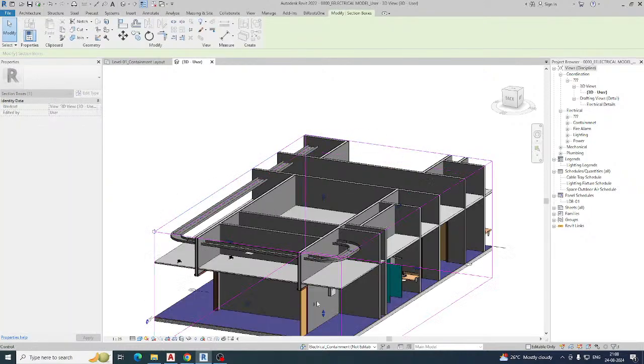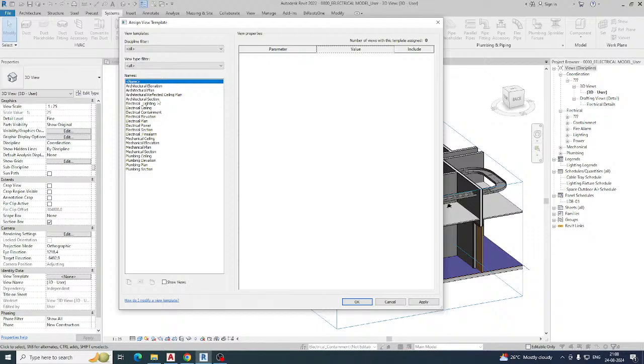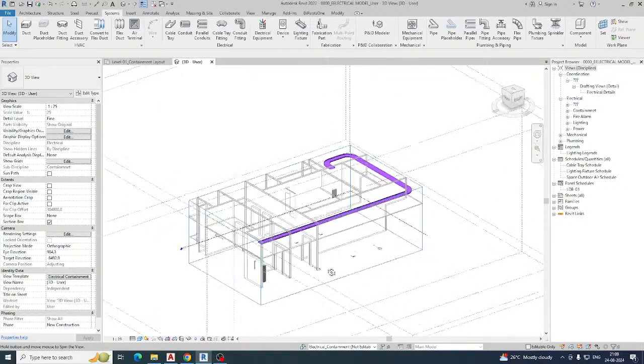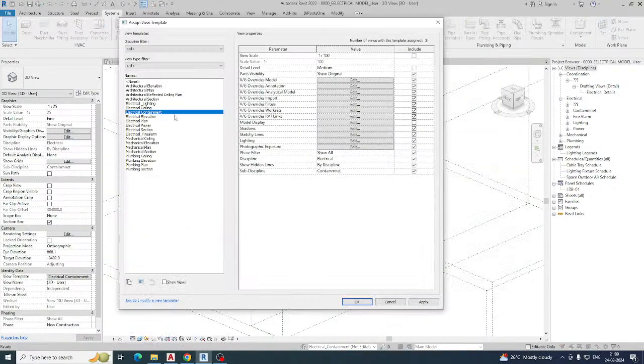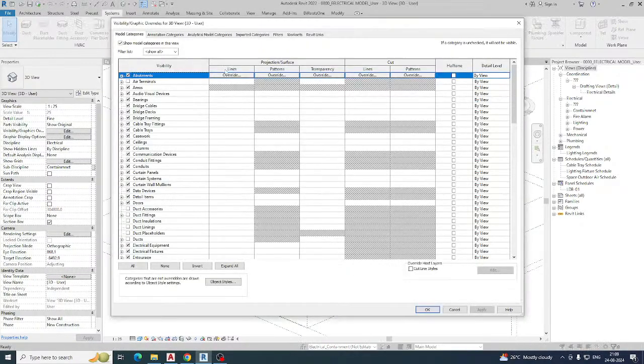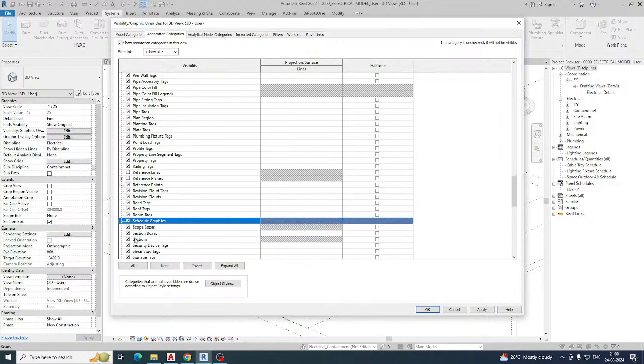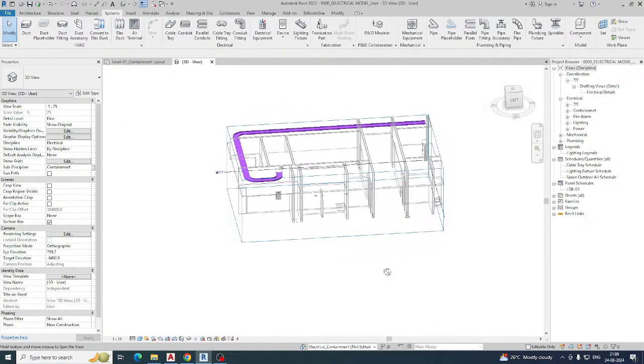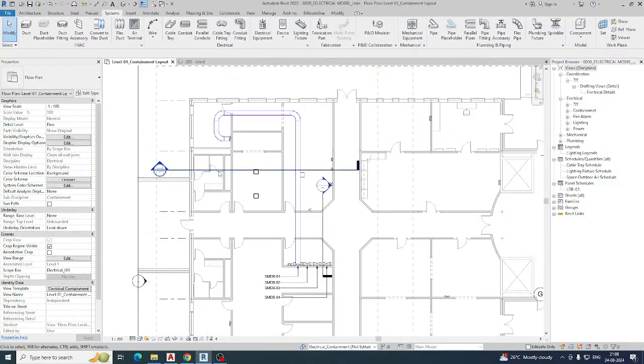You can also apply templates in the 3D view. Use the same electrical containment template here and the colors will be reflected. Go to VV Electrical Settings, set the reference planes and scope box to None, and click OK. You can see the cable tray is now visible in the 3D view.